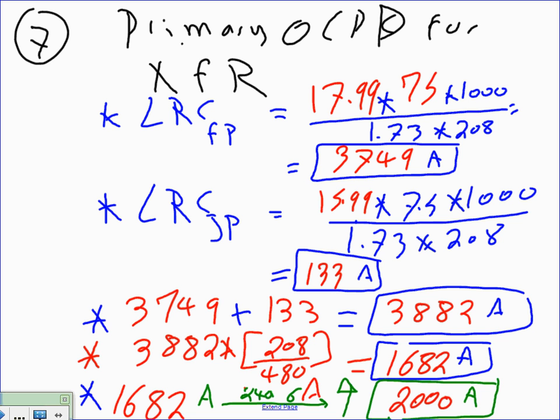So if you, Chris, divide the amps that you came up with by the circuit breaker you got, it gets you 0.8. So if I want to tweak this one, I can actually go 0.84. So I have to go up on these. If I set it at 0.9, then it will give me very close to, if you set this one at 0.9 times 2,000, do I really need a calculator for this? It'll give me 1,800. You set it at 0.9, good to go. You can't set it at 0.95, so 0.9. Okay, we are sizing based on non-adjustable, so we're good to go.